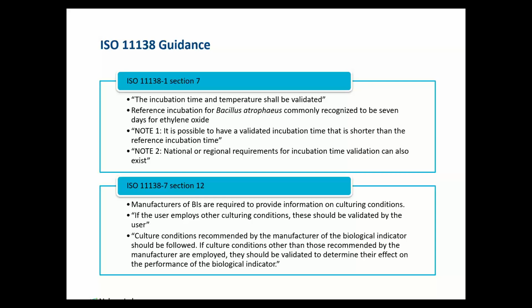It's also noted that the reference incubation for Bacillus atrophaeus is commonly recognized to be 7 days for ethylene oxide, and again, that's what we're most familiar with. But this statement comes along with 2 notes, so this is pulled directly from that ISO 11138-1. The first note states that it is possible to have a validated incubation time that is shorter than the reference incubation time. And then the second note is that national or regional requirements for incubation time validation can also exist.